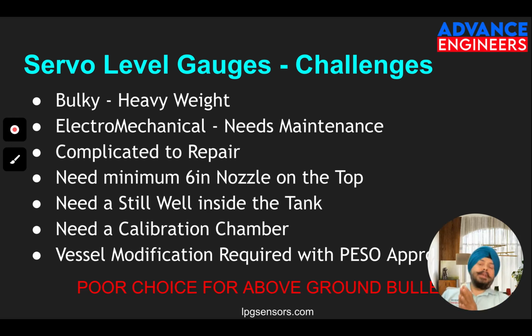To avoid that kind of thing, what we do is we put in a still well. We put a standard pipe which has holes in it, so that it's only carrying the liquid. Even if the liquid is moving and it's turbulent outside, the float remains inside. The float never goes out of that. So you need to have a still well. An SS still well of that particular height has to be installed inside that 6 inch nozzle, because the float has to stay inside. It cannot wander off. So that is one minimum requirement in a servo that you have to put in. Then you need to put in a calibration chamber also, because as I said, it's an electromechanical device. There is wear and tear happening. The sensors are also getting old.